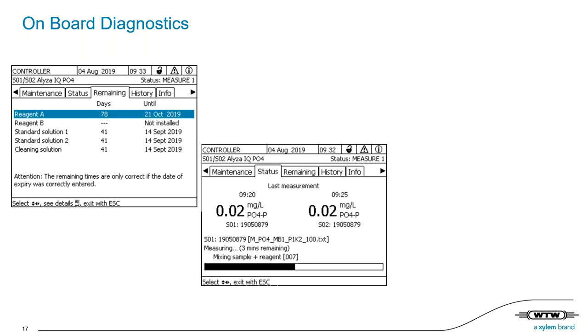The analyzer itself is supplied with the tubings already for the second reagent and for the second standard solution as well. They are not connected, but in case you want to add it now or in future, you can easily connect an additional one, and it's automatic. And you can freely choose the interval for cleaning and calibration. One of our philosophies, of course, is to make life for the person in front of the analyzer as easy as possible. And orthophosphate cannot be measured by sensors to date, so you need a wet chemical analyzer. With the new Alyza, we really included as many steps and features as possible to reduce manual intervention and effort.